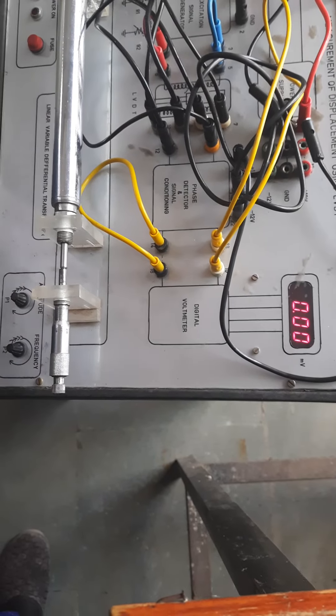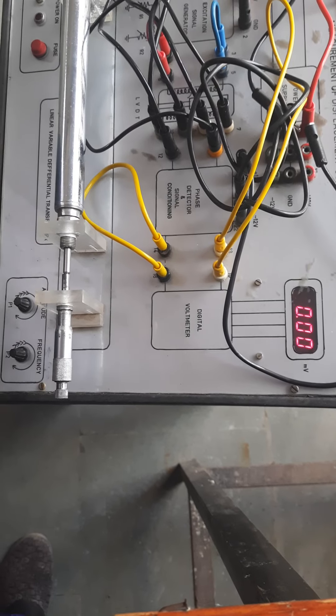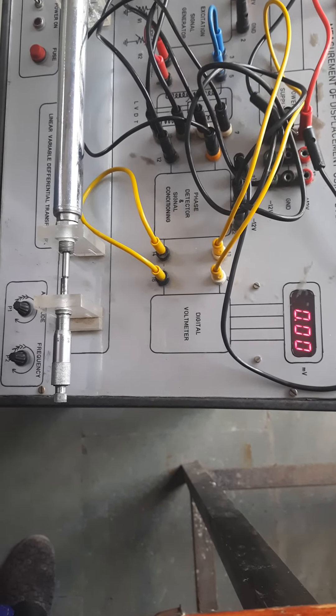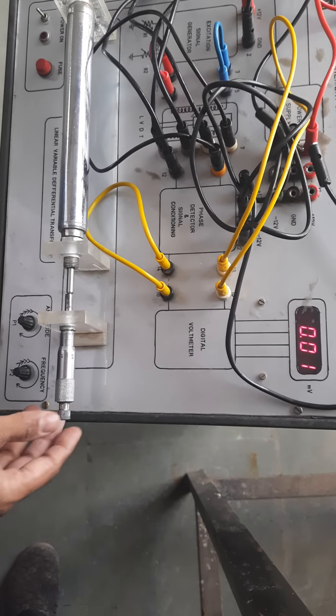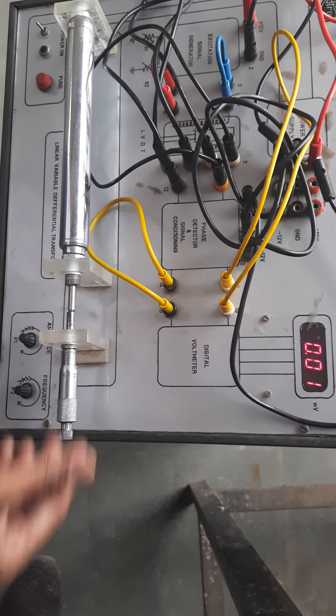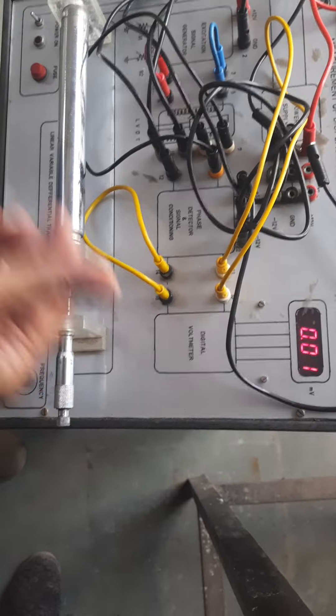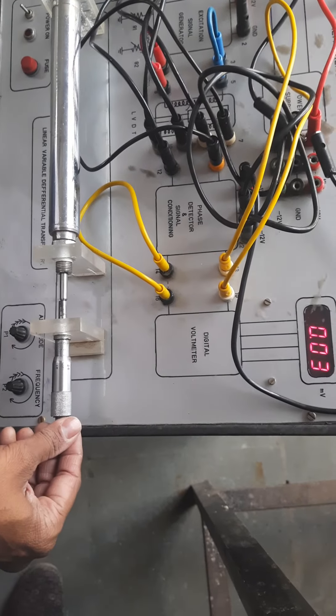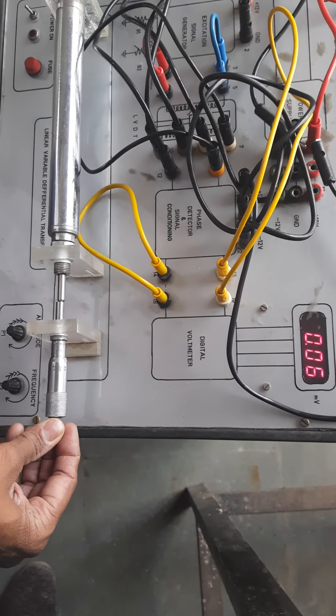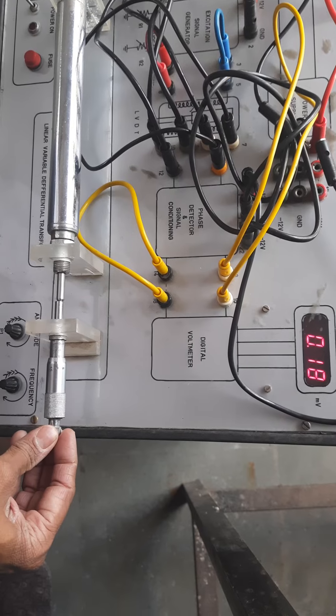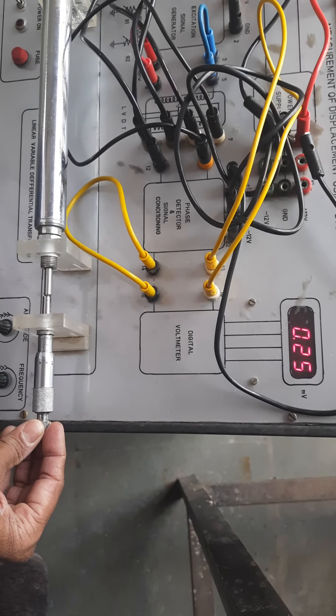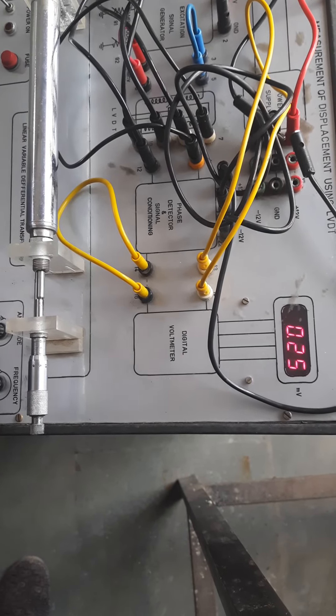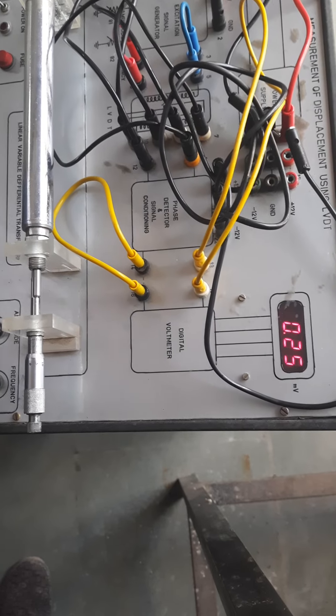Now, suppose you are measuring pressure. So that pressure you are giving to pressure bellows. Pressure bellows will convert that pressure into displacement, linear. And that linear displacement you are giving here. So now, this is above the null position as explained in case 1. So we are moving this. So you can see that, as you move, suppose I am moving from 10 to now, this is 11 mm. So it is 0.25 millivolt. 10 mm was 0 millivolt.